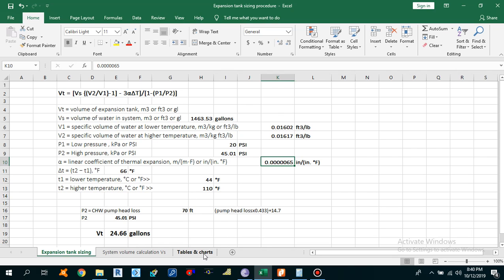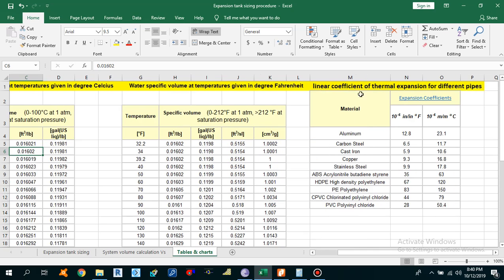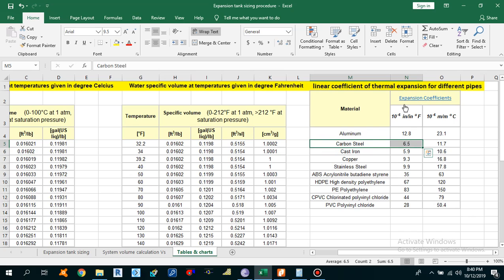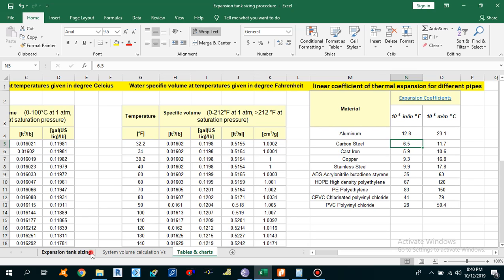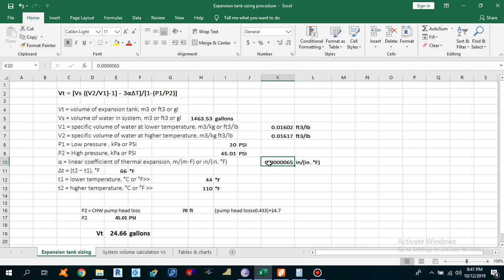This is the linear coefficient of thermal expansion table. As you can see, I have a material list for aluminum, carbon steel, cast iron, and copper, along with the thermal expansion coefficient for each material. Since we are working on a chilled water system using carbon steel, the alpha value is 6.5 × 10⁻⁶ inches per inch per degree Fahrenheit. This is the value we are going to use in our calculation.